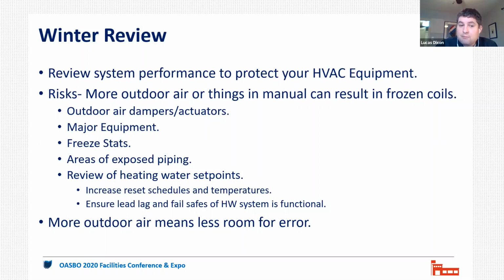We also still have to make sure we remember our major equipment checks. With all the additional responsibilities placed on facilities managers, it's hard to get the normal winter preparations done. Have we fired our boilers and run the lead-lag sequence? Did we properly shut down our chilled water systems? Did we drain our cooling towers, and any exposed piping for water-cooled chillers, etc.? Are there any normal winter preparations we haven't completed just because of all the extra work COVID has put on facility staff?